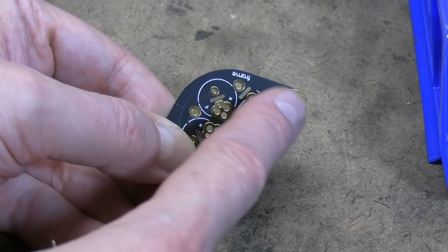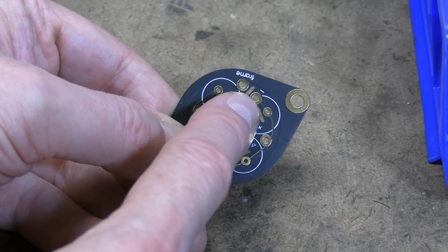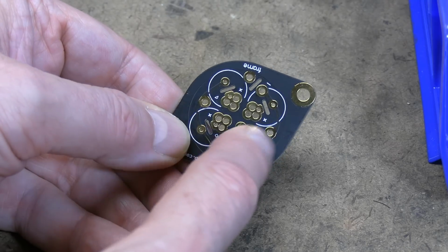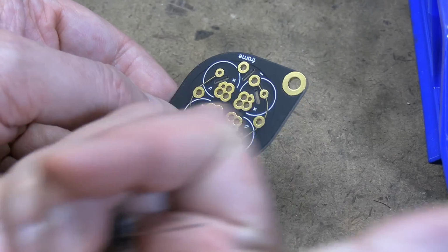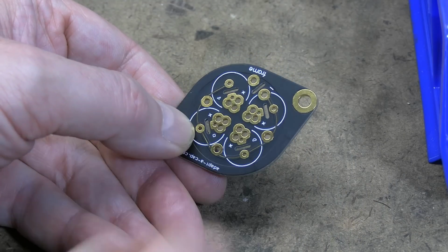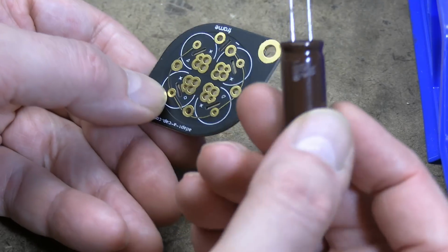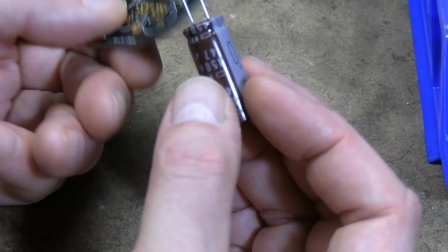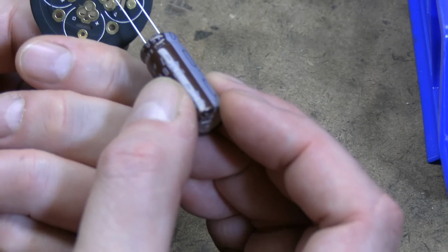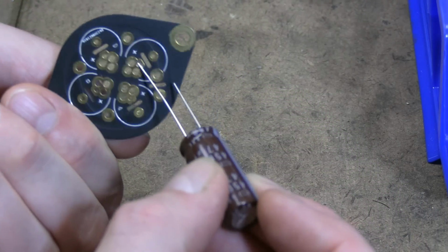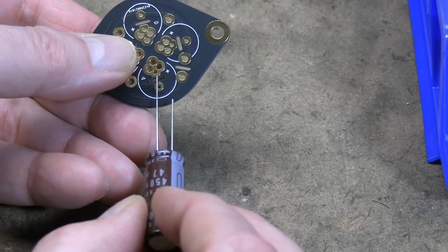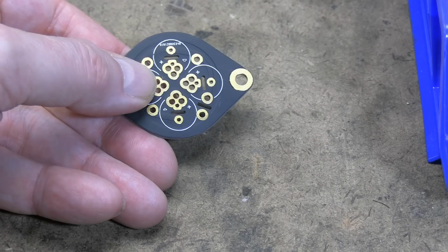Where it says frame, that's going to this, and where it says minus, there's a ring around the outside. That's your negatives, all your negatives go to the outside, all your positives are towards the center. So when you install your cap, you want to put the positive lead in the positive, negative in the negative, and notice there's a slot between them. That is to provide additional insulation.